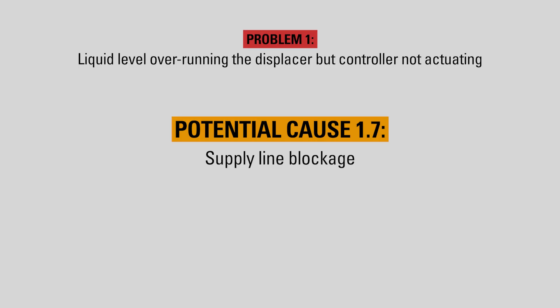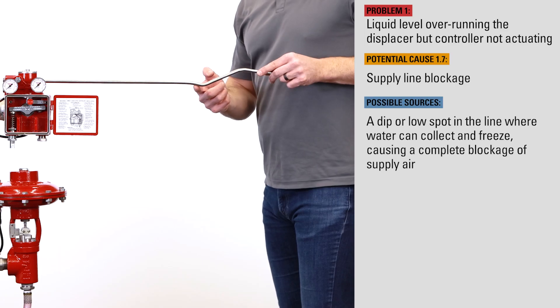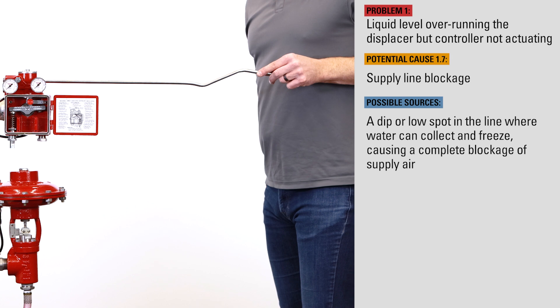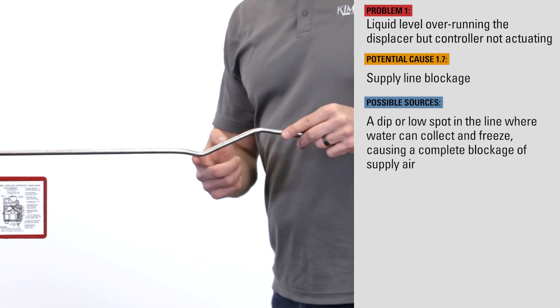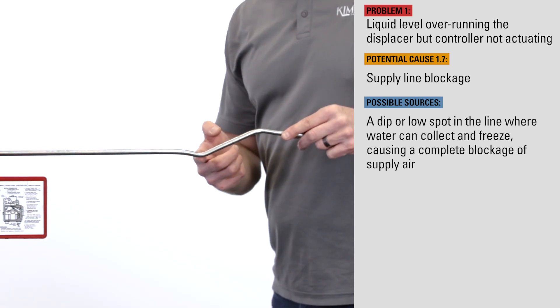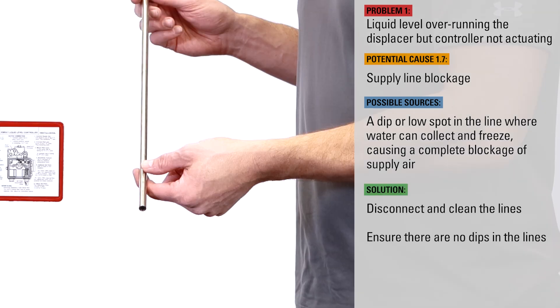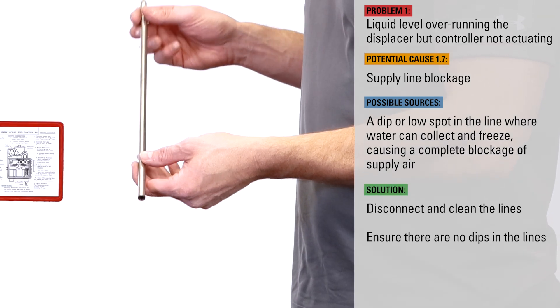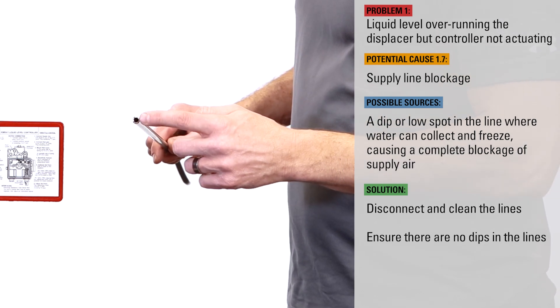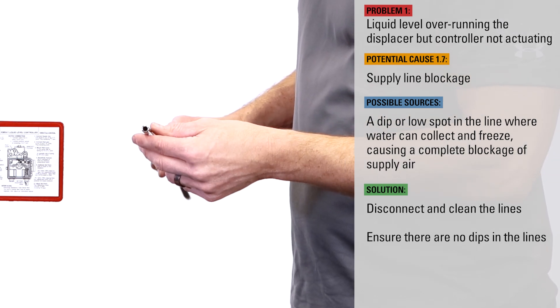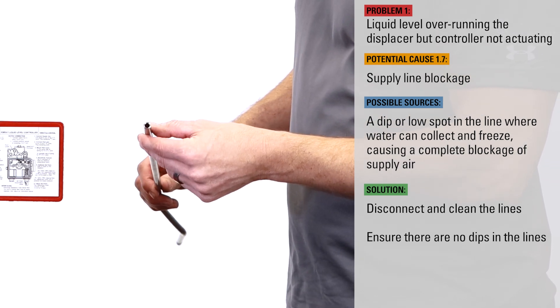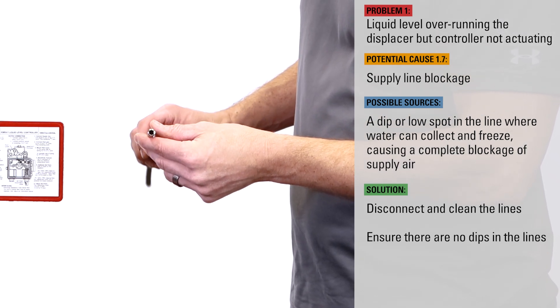Similarly, the supply line could be blocked due to moisture buildup. If there's a dip or low spot in the line, water can collect and freeze, causing a complete blockage of supply air. Disconnect the lines and clean them out. Ensure there are no dips in the lines where moisture could collect and pool.